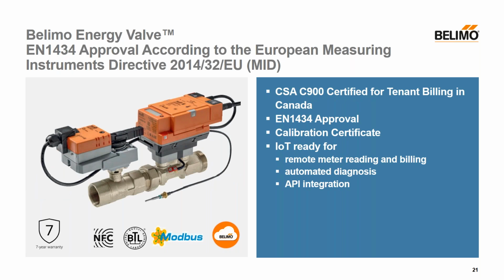Coming later in the second quarter of this year is our MID version of the energy valve, which carries all of the features previously mentioned for the EV4 with the addition of a certification of EN 1434 approval according to the European Measurement Instruments Directive, which is where we get MID. This is a requirement for billing in Europe, but these also carry a CSA C900 certification, which is a Canadian requirement for tenant billing. And this enables our Canadian customers the ability to utilize the thermal energy meter energy valve for billing purposes. These also feature a display that shows thermal units. These are not in the printed PGPL, but will be added to the digital version when released.